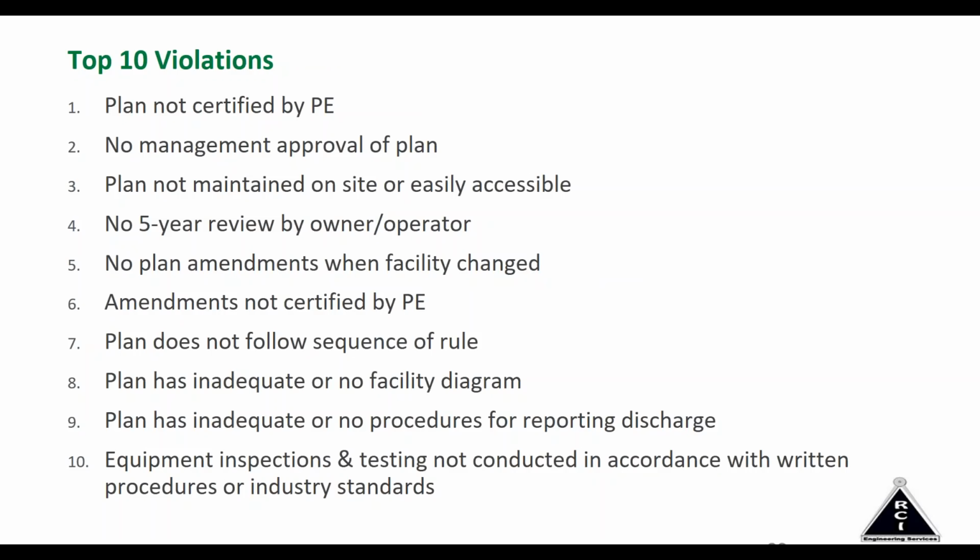No facility diagram. That's a part of the rule. They're getting pretty particular about their facility diagrams. A lot of times, if we can, we'll use aerial or satellite photos, but we'll drop the facility in and identify all the storage containers, what falls under the SPCC rule, and how the surface water of the facility flows, which direction it flows.